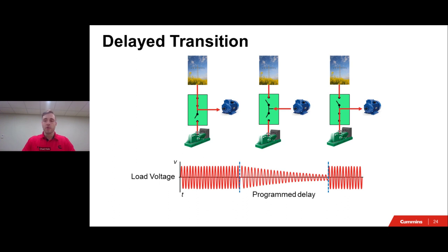So here we can see on the far left of the diagram, you have your normal source and your backup gen. Your gen's on. The automatic transfer switch realizes there's an issue with your normal source. It opens to the normal source, and then the automatic transfer switch goes into its program delay, which is that middle piece. You can see the voltage decaying. Once it has decayed to a reasonable amount, or until that time delay is over, it will then switch on to your emergency power source. This eliminates the feedback of residual voltage.